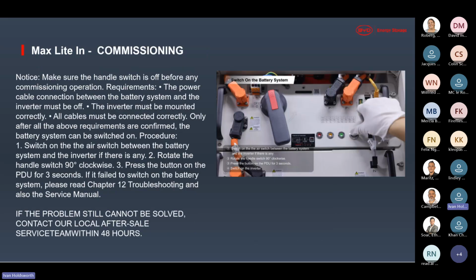And in terms of turning on, this will be the turn on procedure. It's best to make sure that all of your fuses and everything between your inverter and your battery are closed before turning on either the inverter or the batteries. And it's very important not to open any fuses under load, because DC can arc very, very well. Because with AC, as your waveform goes through zero, it kills the arc. DC doesn't go through zero.